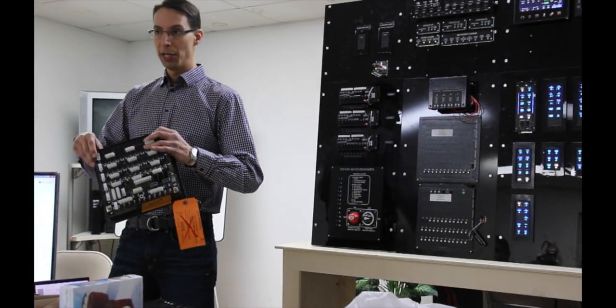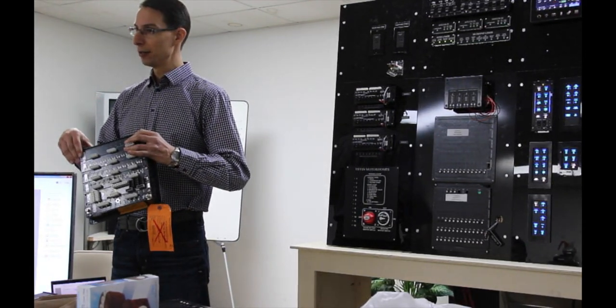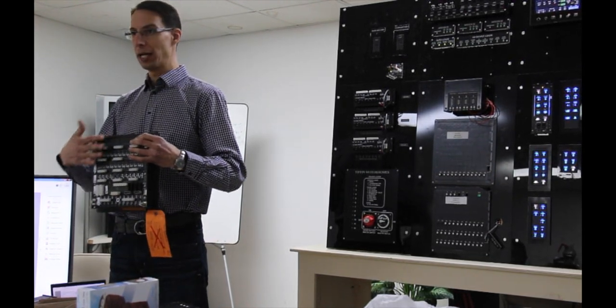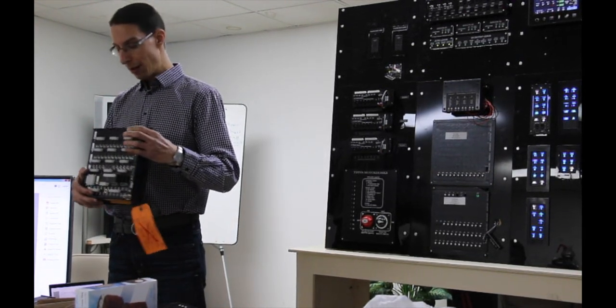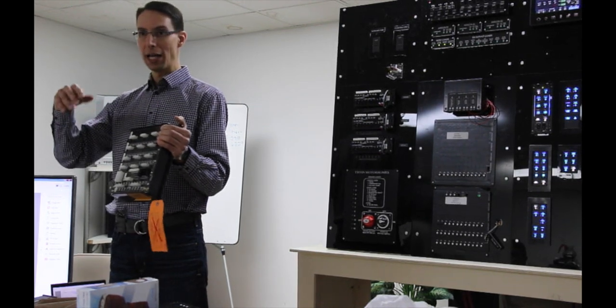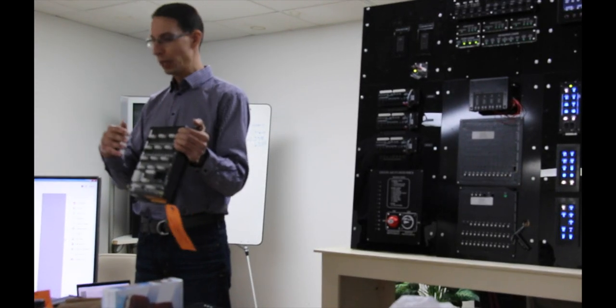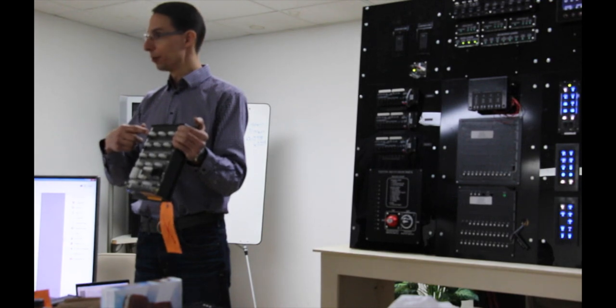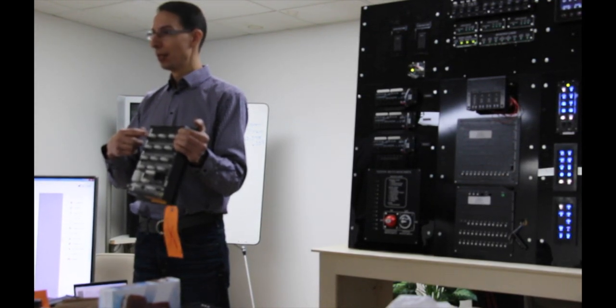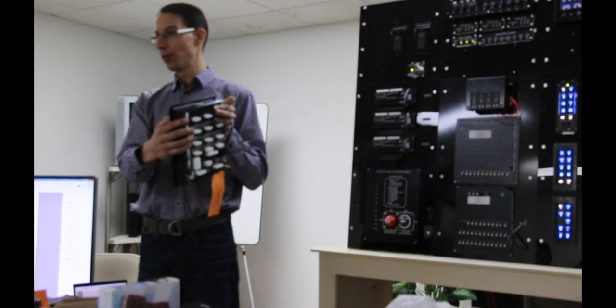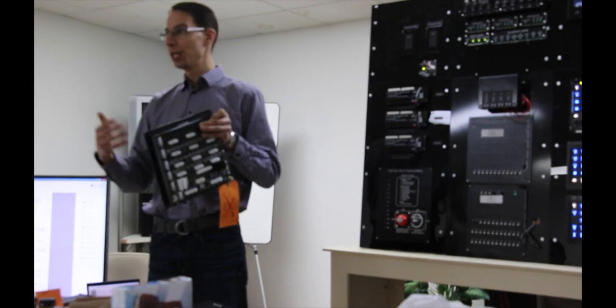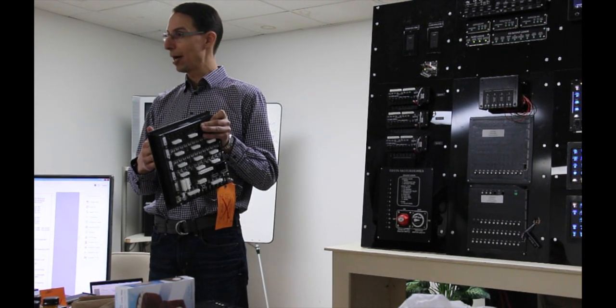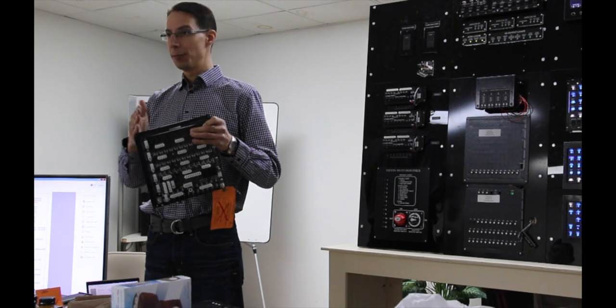We're redesigning this panel to kind of make this all kind of enclosed on the back side. But right now if there was, say at some point during service or even production, something touched one of those little pins and shorted out, it would wreck the channel on the driver card. So those would be examples of where the driver card might get damaged and it would need to be replaced, the whole panel, to address that issue.